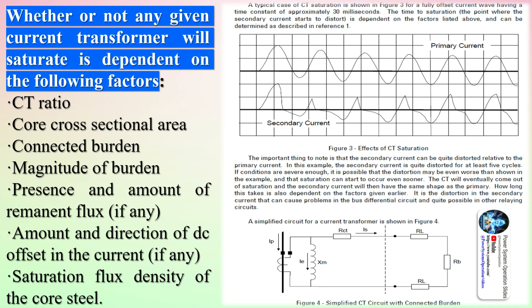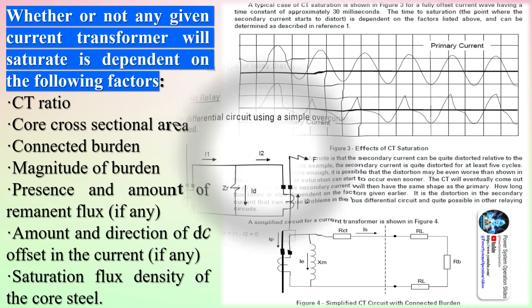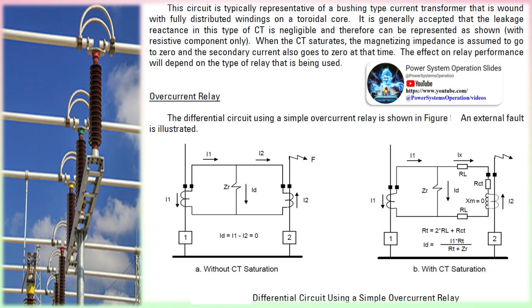In a basic differential system, the current transformer CTs are all connected with the same ratio and polarity sense so that the currents circulate amongst the CTs — ID equals zero for all external faults and load flow — whereas the total fault current ID equals IF will flow through the relay for all internal faults. If the CTs behaved ideally, the differential system would be very easy to implement using a simple overcurrent type of relay. Unfortunately, the CTs may saturate and thus may cause the differential system to operate in other than an ideal way.